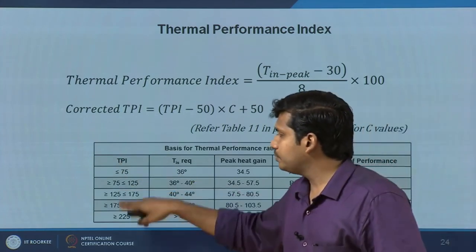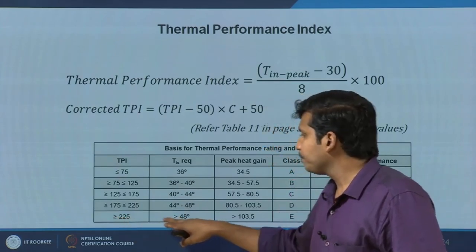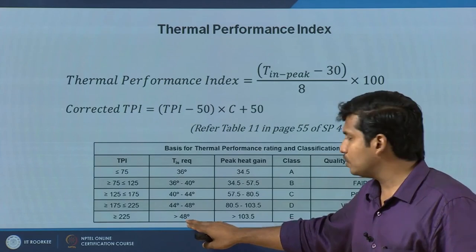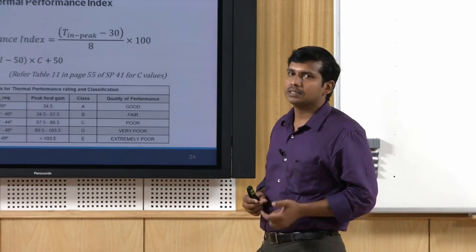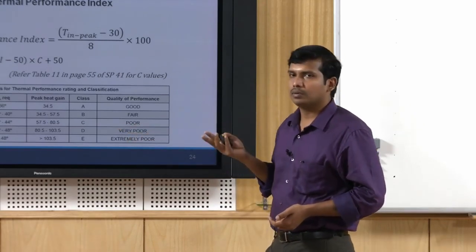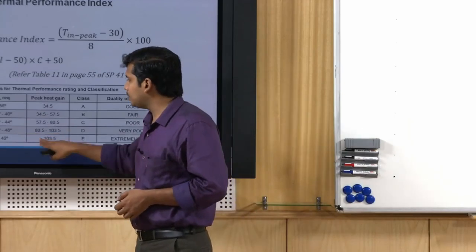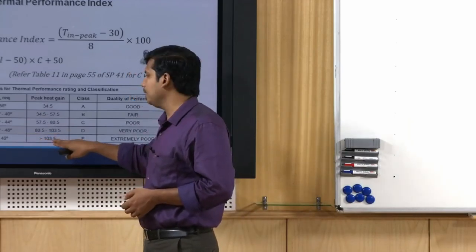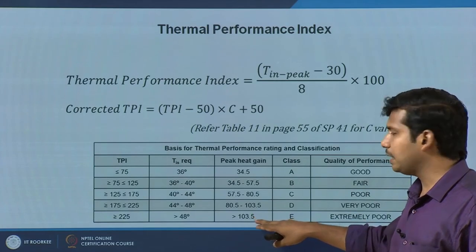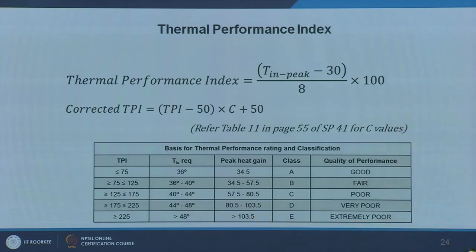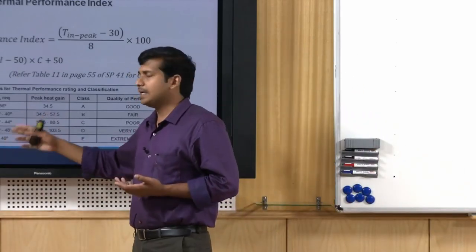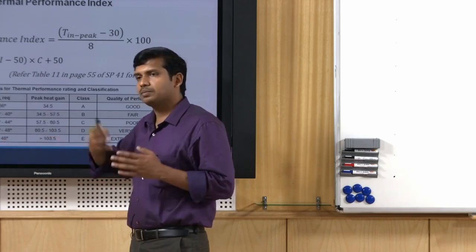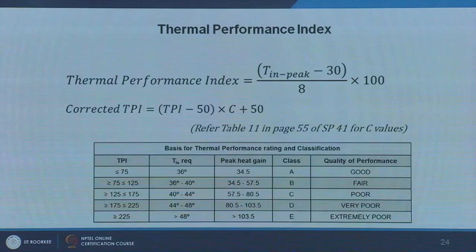If TPI is greater than 225, the inside surface temperature goes above 48 degrees. Touching the wall inside it would reach 48 degrees or above — really uncomfortable. As a consequence, heat gain exceeds 103.5 watts per meter square, which is extremely poor. A thin metal sheet, for example, may reach inside peak surface temperature of 50 to 52 degrees, outside much higher — an extremely poor thermal classification.